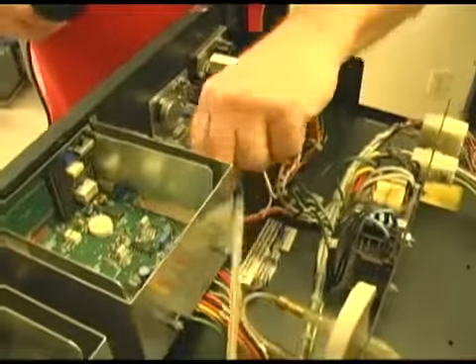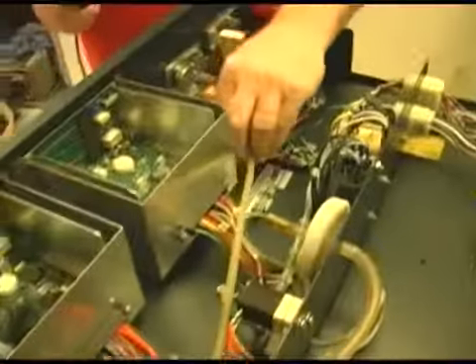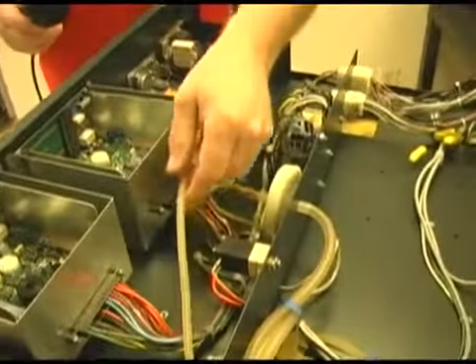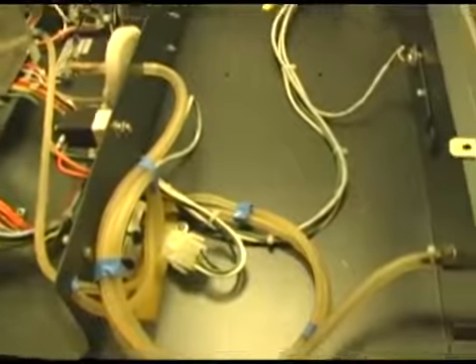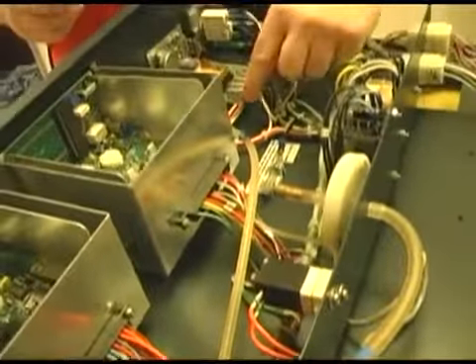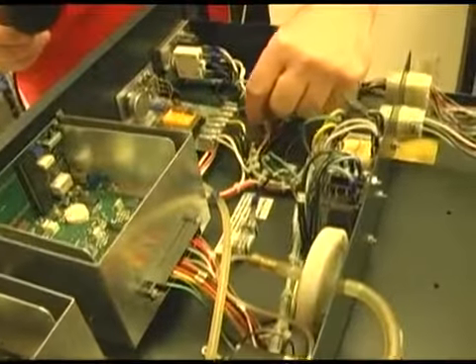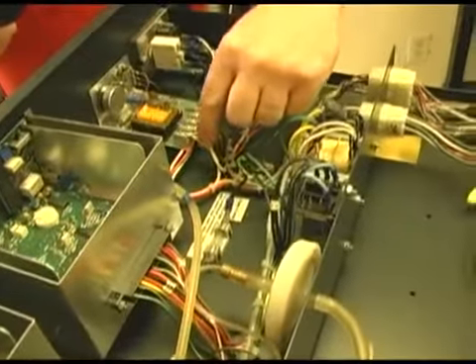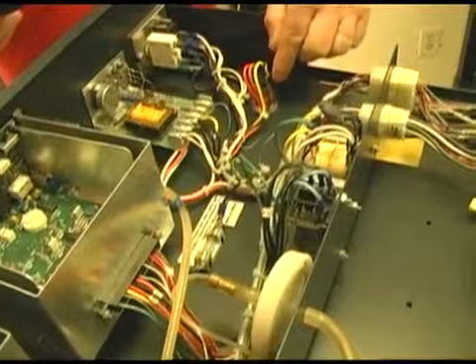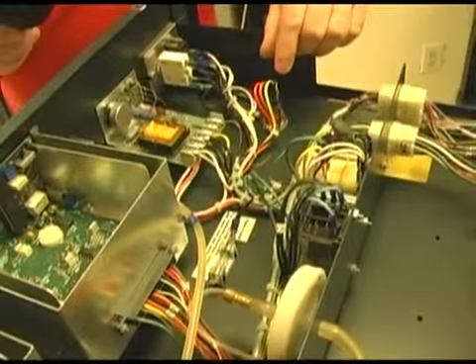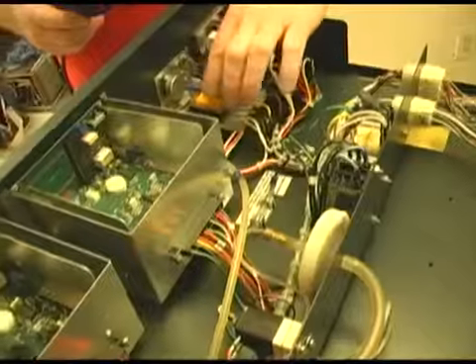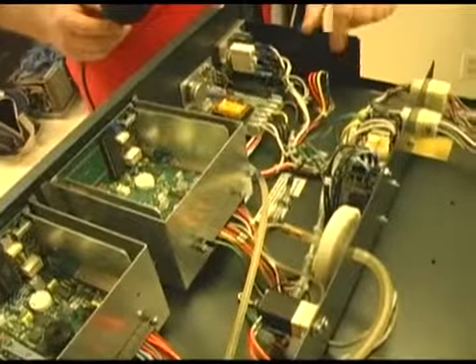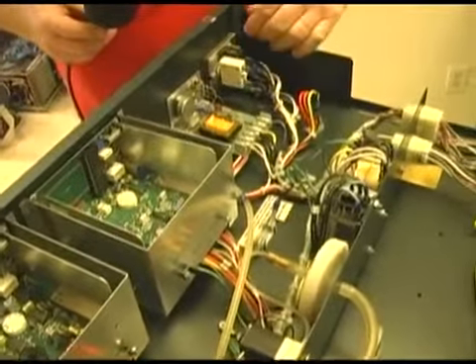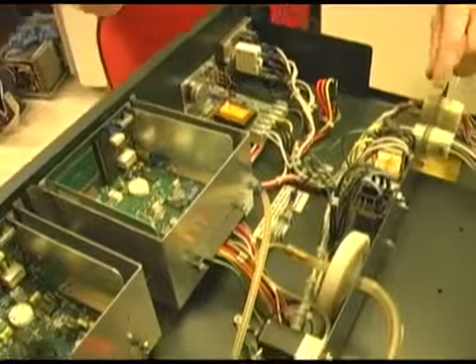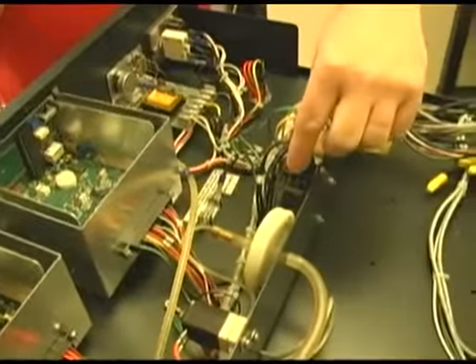Moving over to the tubing that goes to your sample port. This tubing goes right into the chamber. Then you've got your temperature module. The temperature module has power coming into it, and then it has your thermistor. And this cable also goes to a triac, which is what controls the heater. I will mention that if you find out that this is all burned up, you change these as an assembly. Then you've got your circuit breaker and your on-off switch. You also have a transformer and a relay.